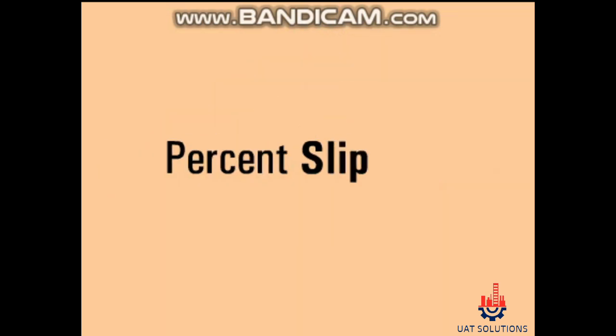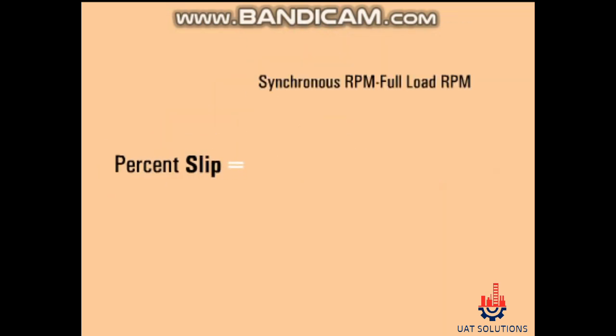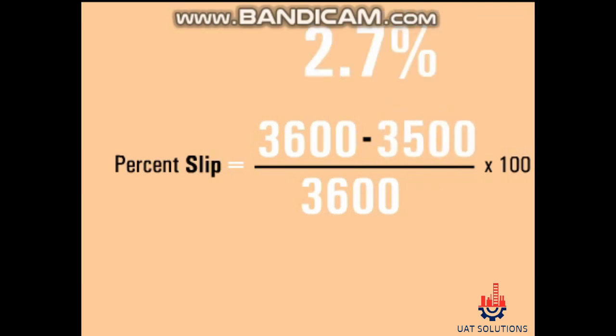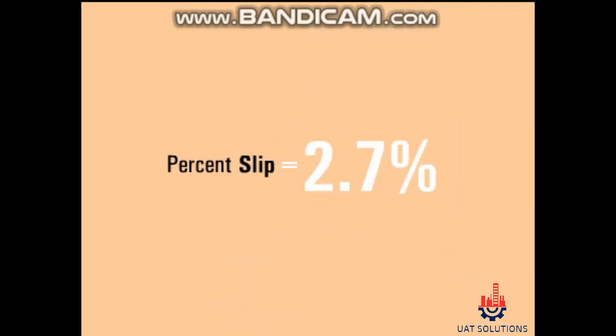Slip is variable depending on the motor design, but for standard NEMA Design B motors, it is 3 to 5 percent, making the typical two-pole induction motor operating at 60 hertz run at 3500 RPM at full load.